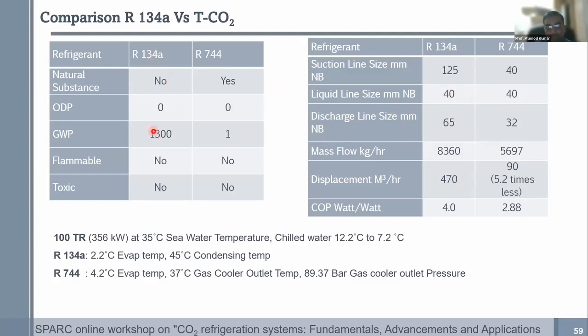When you look at 134A, it is the most popular refrigerant worldwide. So all this comparison is with respect to 134A. For a similar capacity 134A system, your line size is less than half. So although you operate at higher pressures with thicker tube wall thicknesses, your line sizes are significantly smaller. So it significantly shrinks down the system size. Okay.